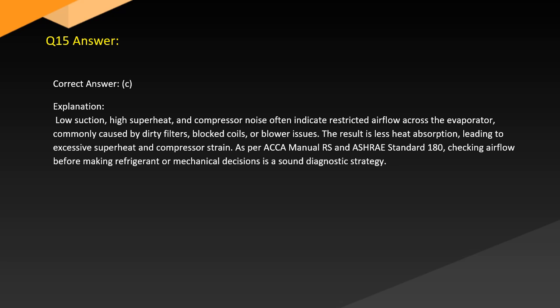Answer. Correct answer: C. Explanation. Low suction, high superheat, and compressor noise often indicate restricted airflow across the evaporator, commonly caused by dirty filters, blocked coils, or blower issues. The result is less heat absorption, leading to excessive superheat and compressor strain, as per manufacturer manuals and ASHRAE Standard 180. Checking airflow before making refrigerant or mechanical decisions is a sound diagnostic strategy.